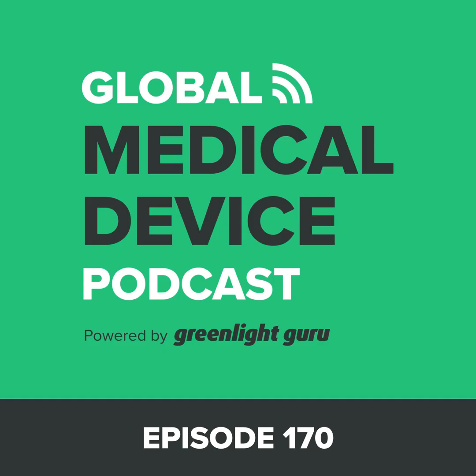And what we found in this pre-sub process is that no matter how detailed we make this device description, there's still always questions that reviewers have. There's still something that they sometimes misunderstand. They're humans too, right? And they have limited time to read through these things. And sometimes it's a thing that we did leave out or we didn't think about, and they just want more information about it. So these pre-subs are really critical to describing your device, making sure the FDA is comfortable with it, familiar with it, so that when it does get time to doing that full market submission, they can breeze through it. They know exactly what your device looks like, what it does, what it feels like, what are the risks associated with it.